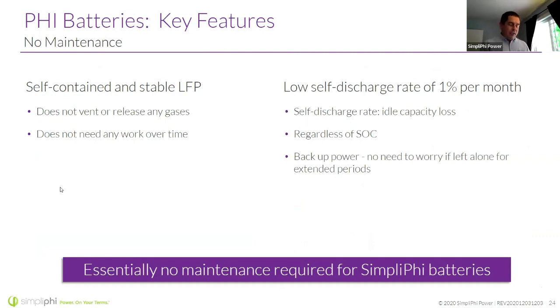A big feature, if you're coming from the lead acid world, is maintenance. With a lead acid bank, you may be familiar with watering your batteries or shooting the gravity to measure the electrolyte to see if they needed more electrolyte or water. It's a lot of opening of caps, messing with battery acid, so there's a lot of PPE requirements like gloves and goggles and other stuff. With our battery, there's no maintenance. You don't have to go back to the batteries and do a maintenance contract. You can install them, set their set points, and know they're going to work.